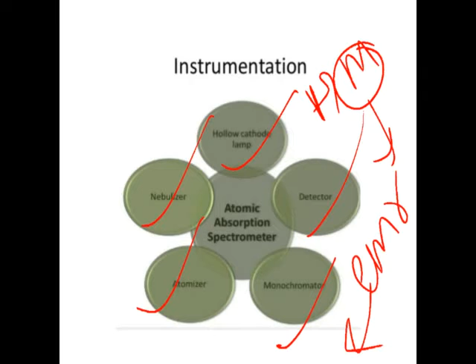So the electromagnetic radiation which comes from the hollow cathode lamp falls on the sample, and when it falls on the sample, the sample absorbs some intensity of this electromagnetic radiation, and some intensity is transmitted. This transmitted radiation passes through the monochromator, then it goes to the detector for the detection of the intensity of the passed electromagnetic radiation, and from that they come to know what the substance is and in what quantity the substance is present in the metal.